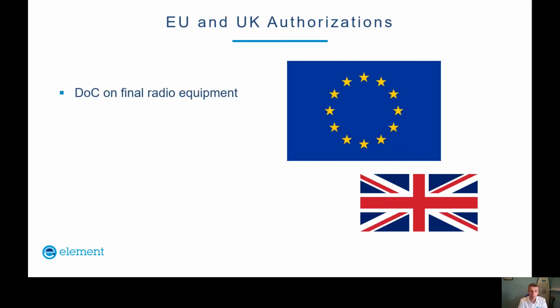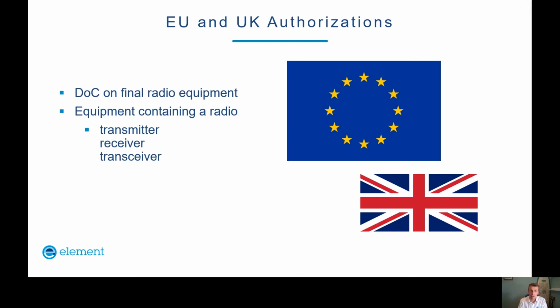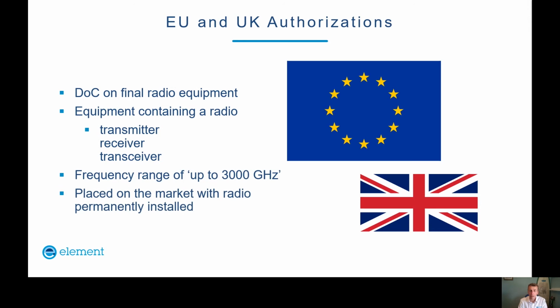A recap then about the EU and UK requirements: a declaration of conformity is needed on final radio equipment - any equipment containing radio transmitters, receivers, or transceivers, with a frequency range up to 3000 gigahertz. This covers devices placed on the market with radio permanently installed. For example, in front of me I have a laptop. Imagine it was a very basic laptop with no radio feature whatsoever - that laptop would be covered by the EMC Directive and the Low Voltage Directive, not the Radio Equipment Directive, because it isn't radio.